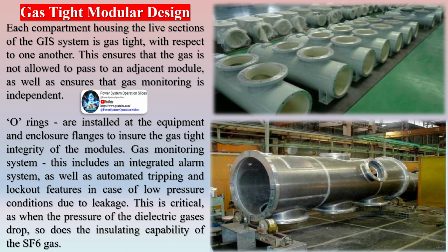Each compartment housing the live sections of the GIS system is gas-tight with respect to one another. This ensures that the gas is not allowed to pass to an adjacent module, as well as ensures that gas monitoring is independent. O-rings are installed at the equipment and enclosure flanges to ensure the gas-tight integrity of the modules. The gas monitoring system includes an integrated alarm system, as well as automated tripping and lockout features in case of low-pressure conditions due to leakage.